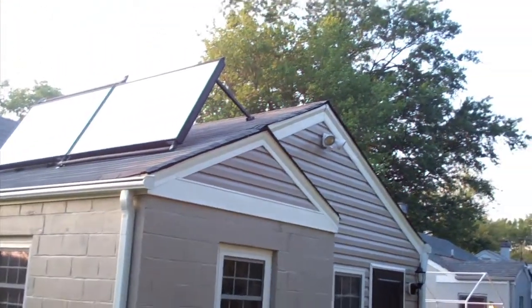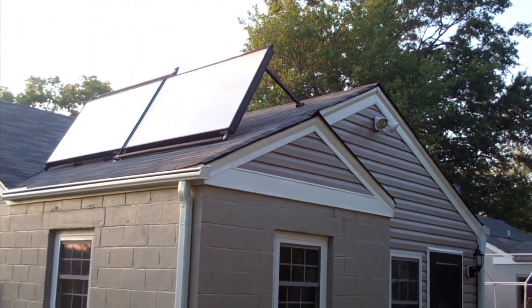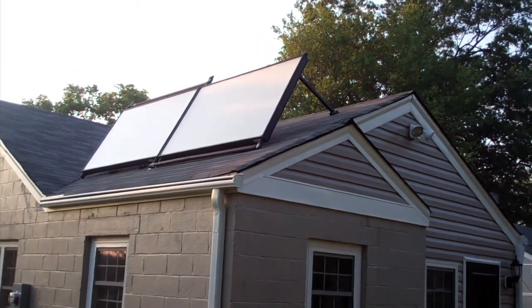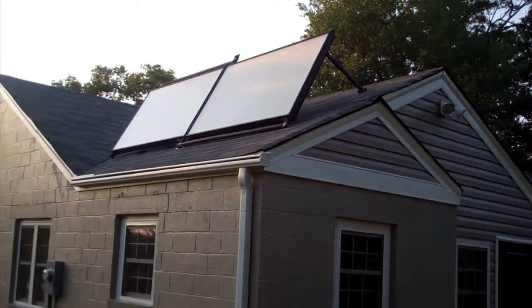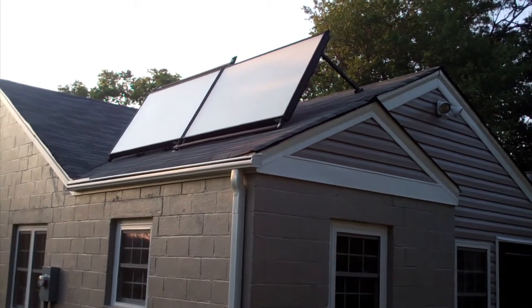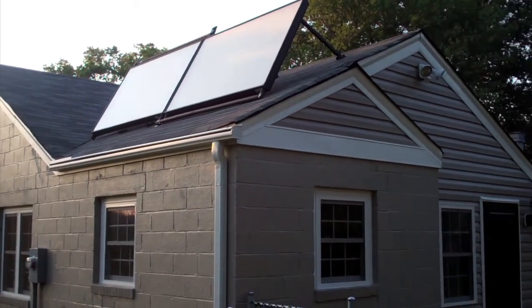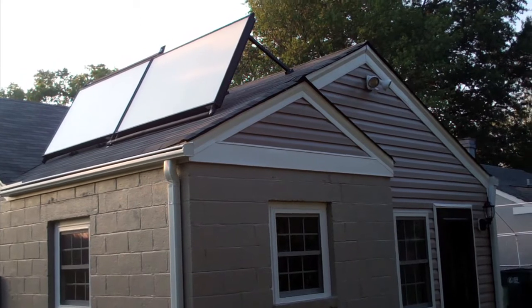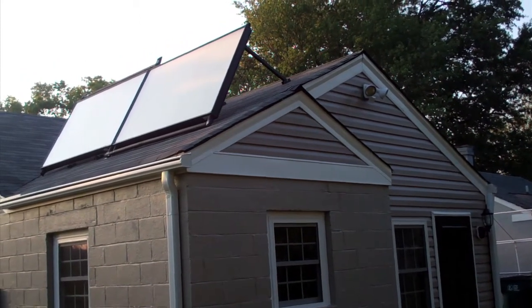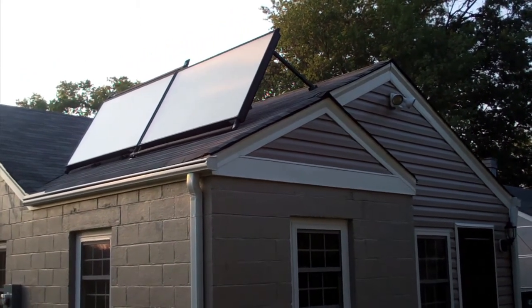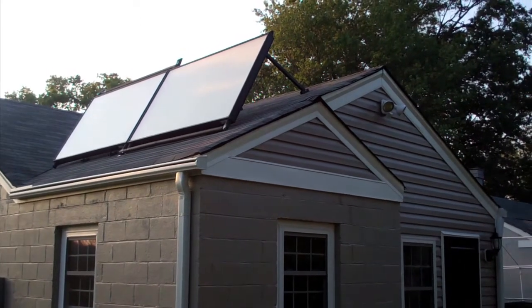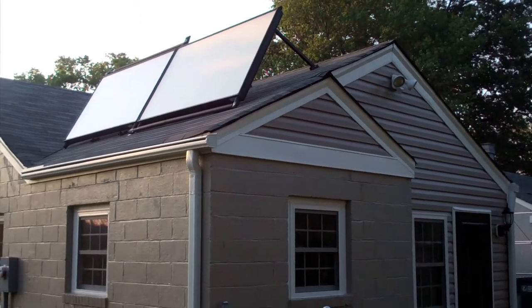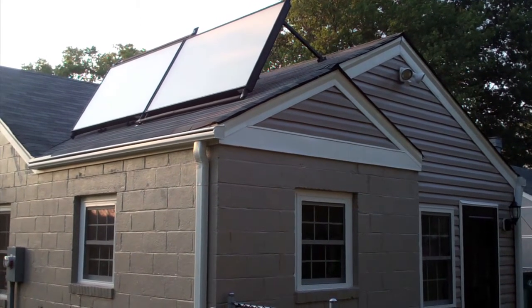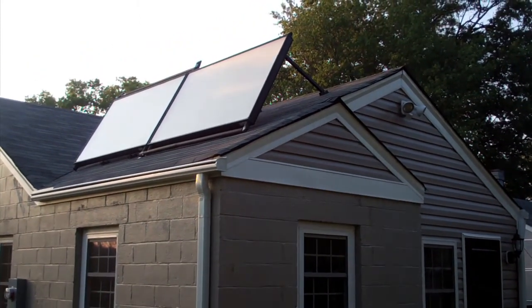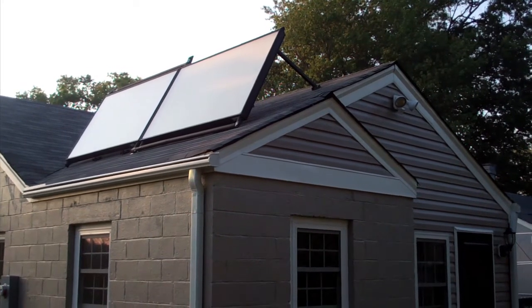Here we are at a Habitat house in Henrico, Virginia. This was done this summer. These are two 4x6 panels installed in a landscape mode, not portrait like normally done. And these are up at a 60-degree angle. You can see they're elevated from the roof. And that's because we're using them to do space heating in the winter. In the front living room, there's radiant floor installed, and these provide heat in the winter to that floor.